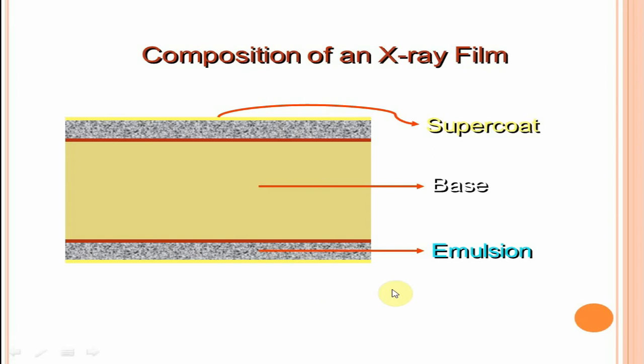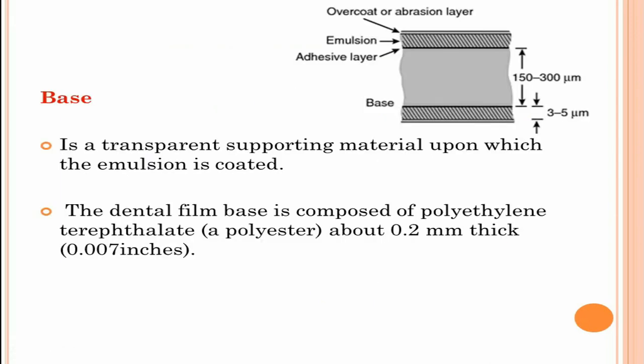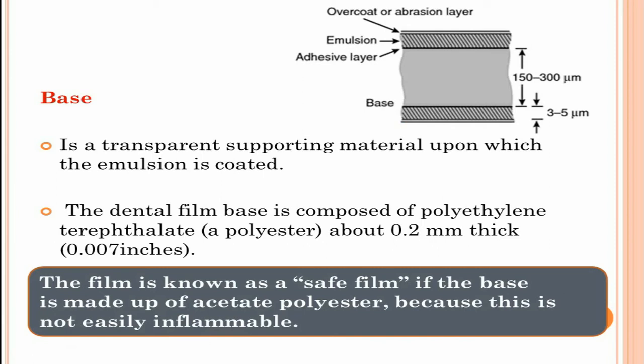First is the base, a transparent supporting material upon which the emulsion is coated. The dental film base is composed of polyethylene terephthalate about 0.2 mm thick or 0.007 inches. For optimal viewing of diagnostic detail, the film base should have a bluish tint and be uniformly translucent, casting no pattern on the resultant radiograph. The film is known as a safe film if the base is made of acetate polyester because it is not easily inflammable.